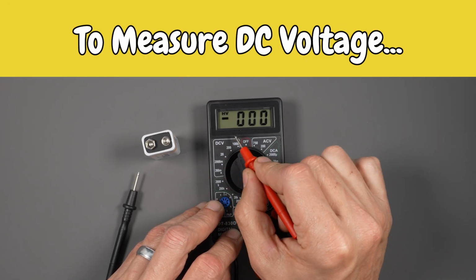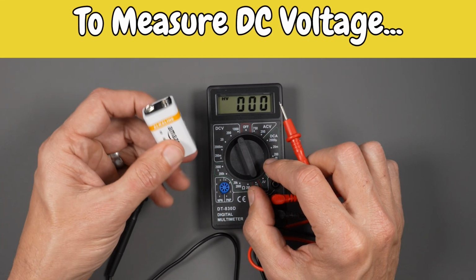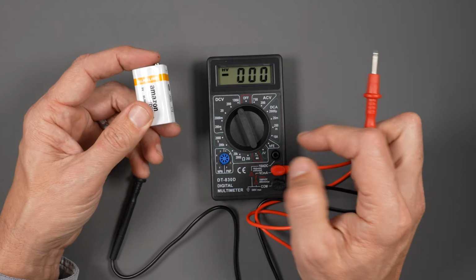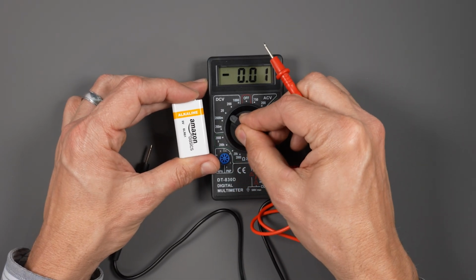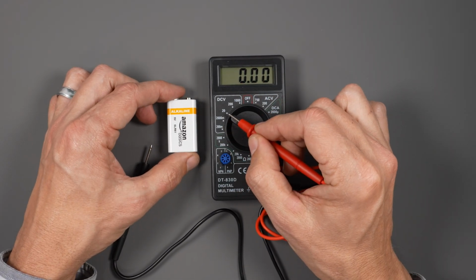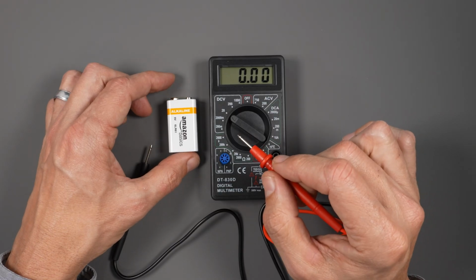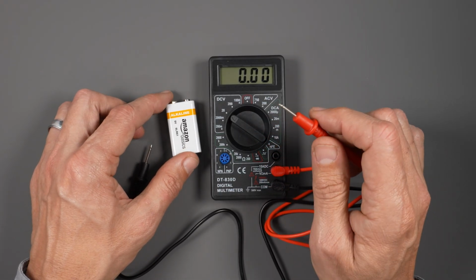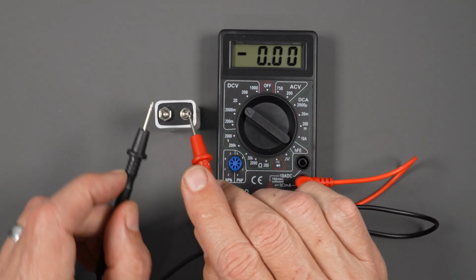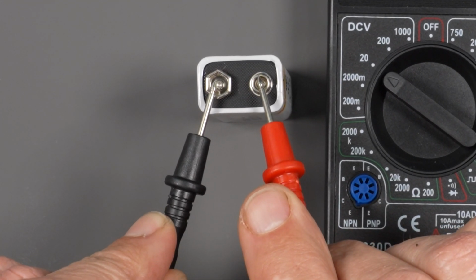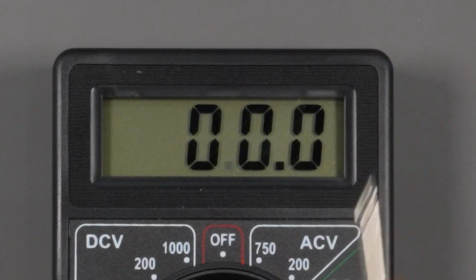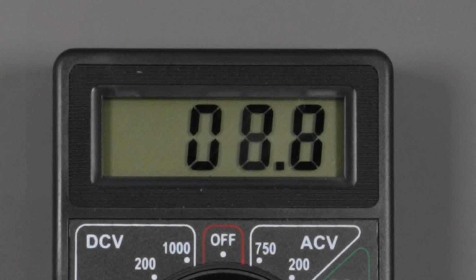To measure the DC voltage, set the dial to the appropriate direct current voltage range on the face of the multimeter. We'll start with a 9-volt battery, positioning the dial to the 20-volt position, meaning it's measuring up to 20 volts. Place the red probe on one terminal of the battery and the black probe on the other. The digital display will indicate the voltage difference between the probes, which in this case is measuring 8 volts. It's probably time to replace this 9-volt battery.